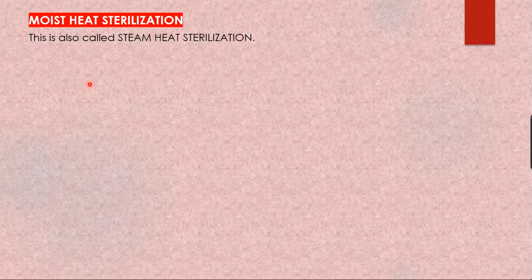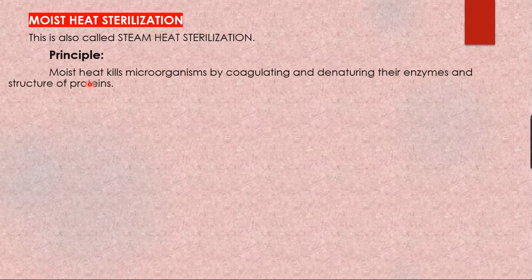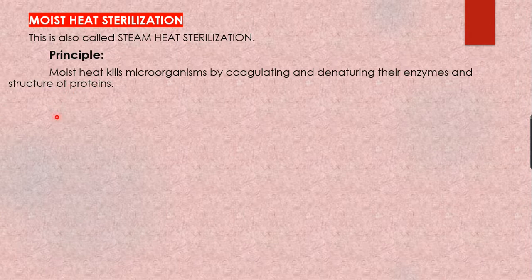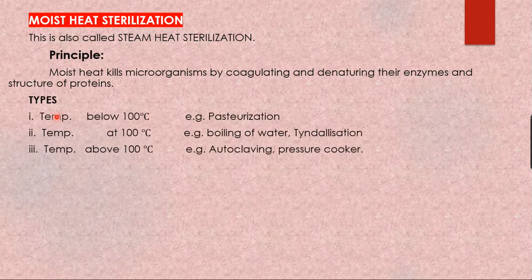Moist heat has a higher penetrating capacity compared to dry heat, which is why it has more impact on damaging cells. Heat in the form of saturated steam under pressure is the most practical method of sterilization, with the best example being the autoclave. Moist heat kills microorganisms by coagulating and denaturing their enzymes and protein structures. Now let's look at the various methods of moist heat sterilization.